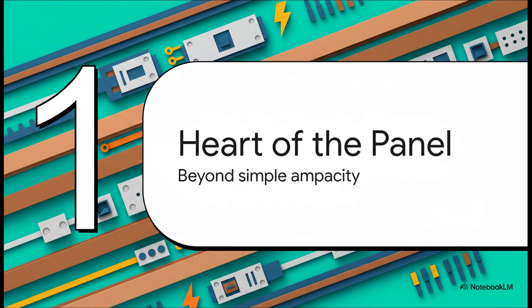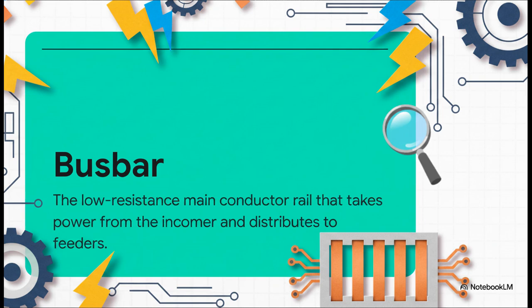All right, Section 1, the heart of the panel, going beyond simple ampacity. We really need to look beyond just simple ampacity to understand the foundation of a switchgear assembly. By definition, a busbar is the low-resistance main conductor rail that takes power from the incoming supply and distributes it out to the functional units or feeders. But what's genuinely fascinating is that compared to your standard cables, busbars are used in these high-current, low-voltage panels because they offer way lower impedance, much better mechanical restraint, cleaner routing, and far more predictable behavior during a short circuit. They effectively manage heat flow and honestly allow for a much more compact panel footprint.